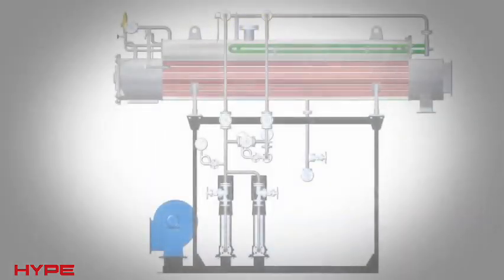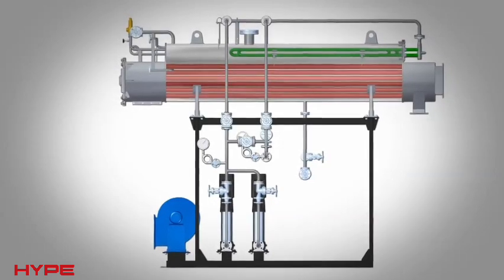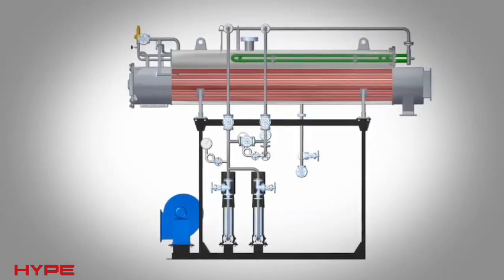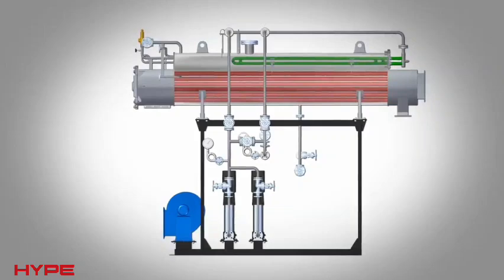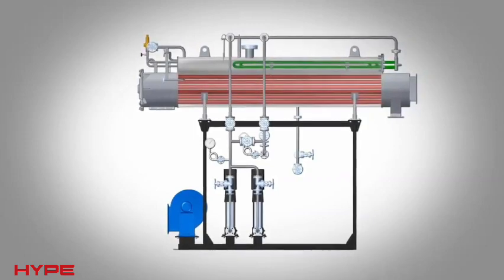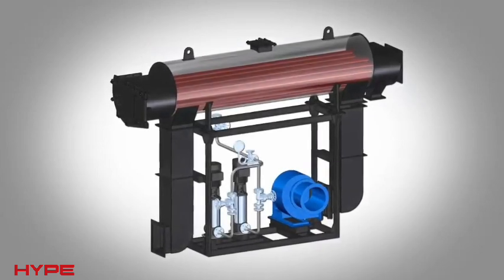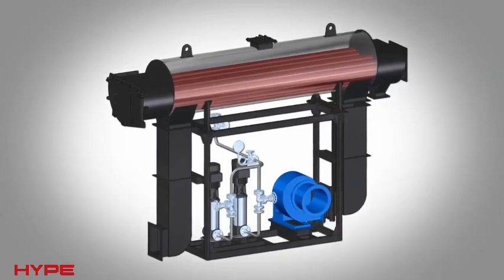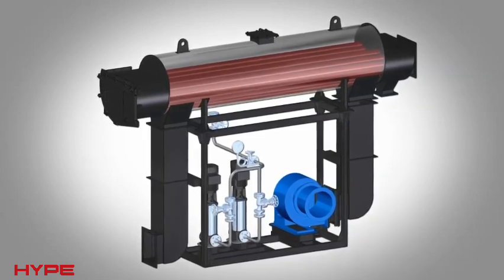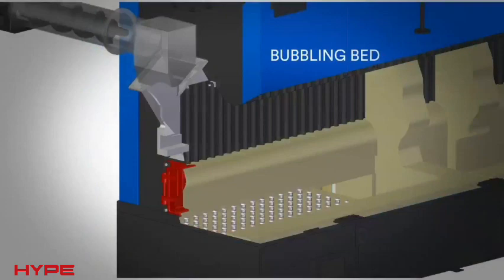The heat recovery unit is used to preheat boiler feed water or the combustion air by using the heat of the flue gases. In turn, they increase the efficiency of the boiler. In the Comblock boiler, a waste heat recovery unit (WHR) is used to preheat the feed water, or an air preheater (APH) is used to preheat the combustion air.